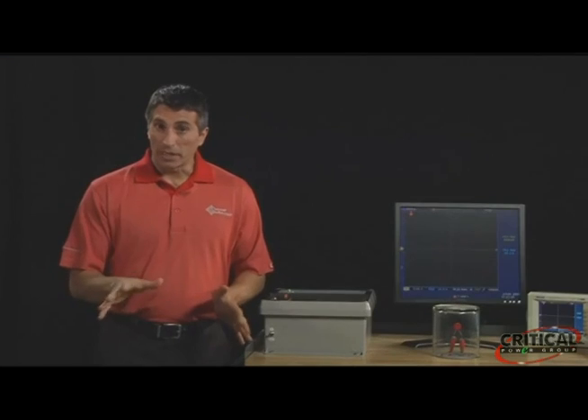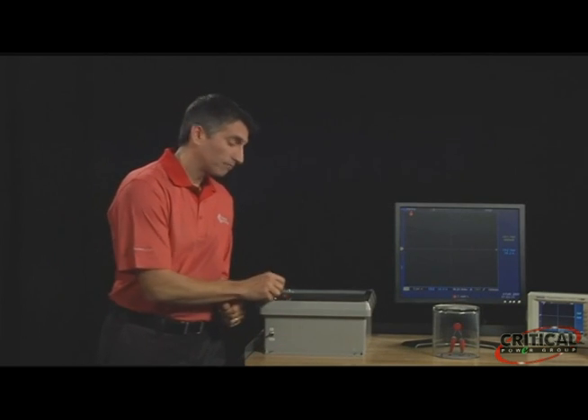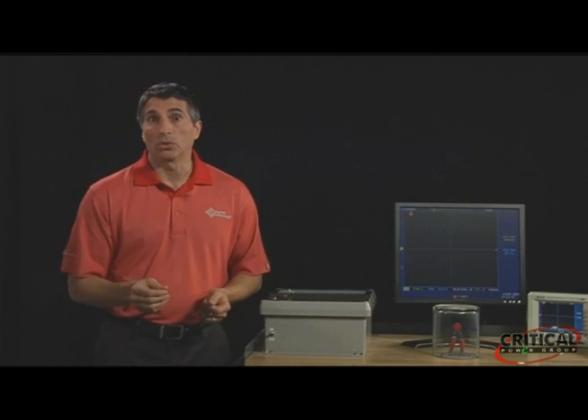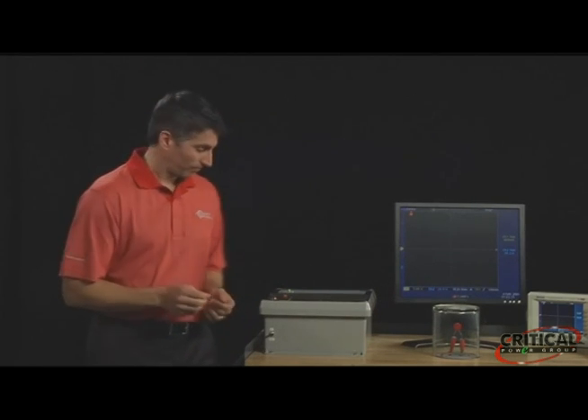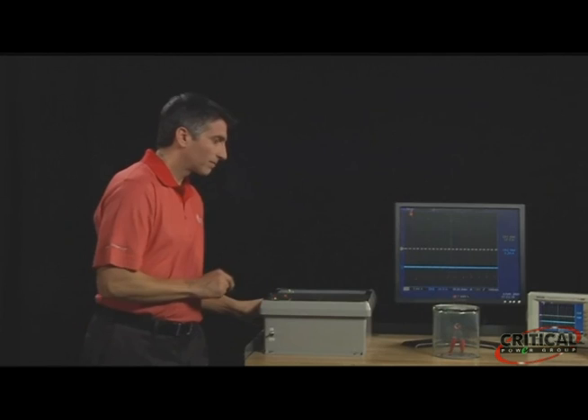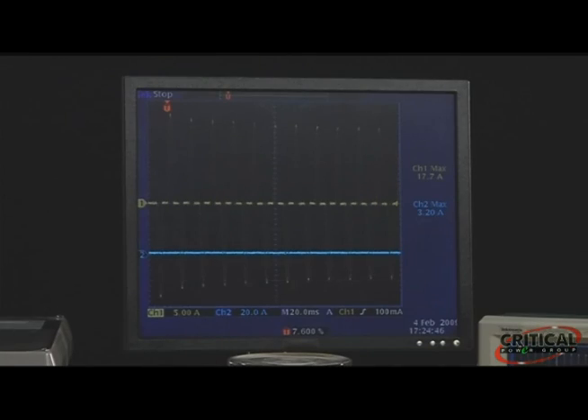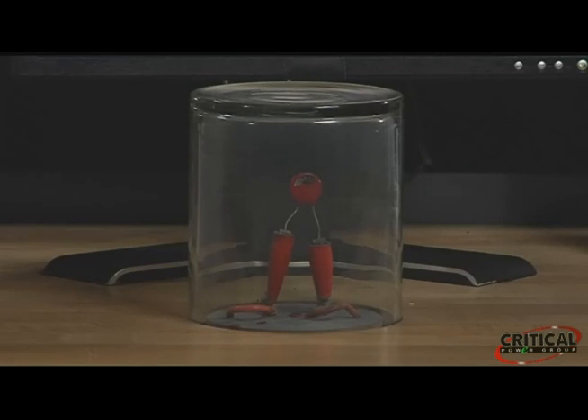Let's leave the voltage right here at 270 volts and remove the selenium cell from the circuit. What do you think will happen when the MOV is subjected to a 270 volt event without the selenium cell? As you can see, when the MOV is subjected to the 270-volt TOV event without the selenium cell in the circuit to protect it, it fails.